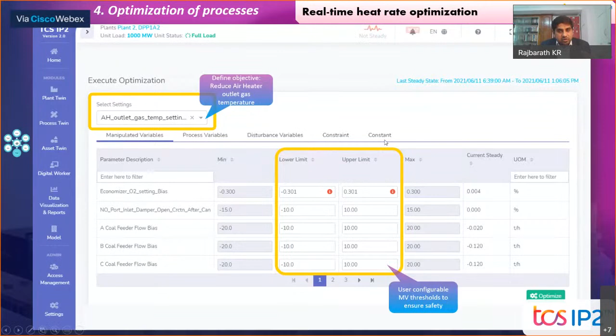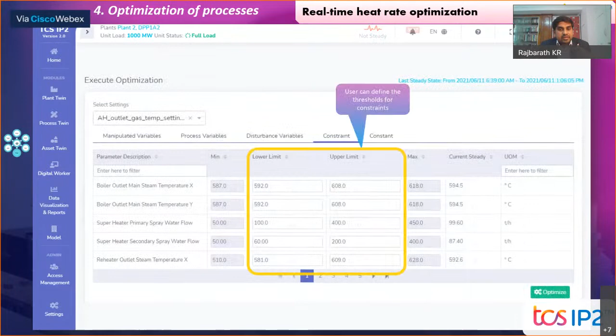On the optimization, right, this one is key, where the objective which we took here was air heater outlet gas optimization. That was the priority for them to reduce the heat rate. And here, the most important thing is they wanted to put it within certain constraints. So they can define the constraints for upper and lower limits for their set points. And within those constraints, the system runs the optimization and it gives the recommendation to the operator. As you can see here, it gives the recommendation to the operator, which can in turn be fed to the DCS system. So it's a complete optimization for a particular objective, which is reducing the air heater temperature.